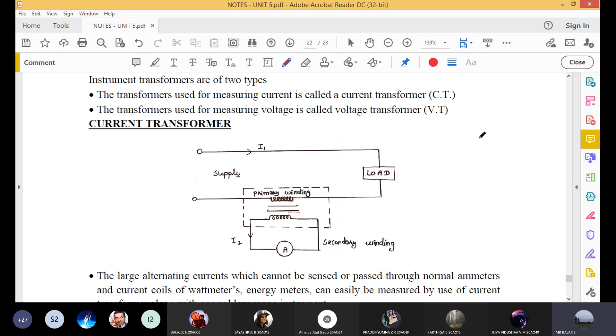For example, if it is 200 volt or 300 volt or up to 1 kilovolt, you can measure it using a normal multimeter or voltmeter. But if I want to measure 66 kilovolt, is it possible using a voltmeter or ammeter? It is not possible, or that equipment will be damaged. So you use a potential transformer which steps down the 66 kilovolt to some standard voltage, say 200 or 300 volt. This 200 volt is proportional to the 66 kilovolt. If it is 100 volt, it will be 33 kilovolt. If it is 50 volt, it will be 16.5 kilovolt. Like that, you can calibrate and measure the voltage.